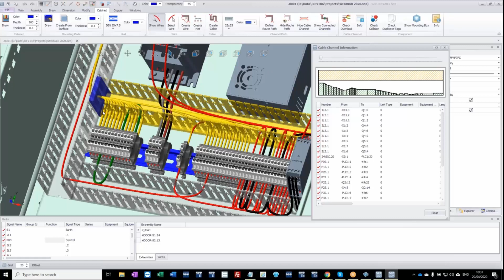So for each cableway, if I click on that one, it's already selected, go into its properties. I can see at the top the channel area size, the density factor, and the channel occupancy. If I want to allow for 40% spare, I can set it to 60% occupancy, and it's probably going to be a little closer but still enough space in there. So I've got 40% spare, and I can see this first bit on the left is where I've got the most cables.